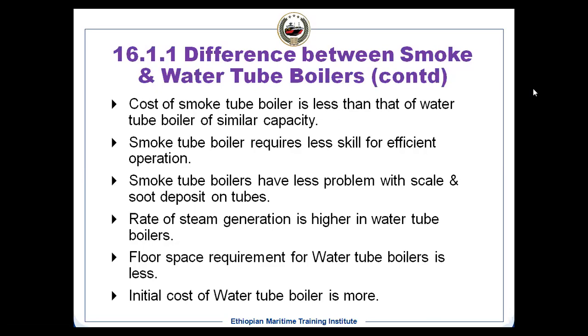Firstly, the water quality has to be maintained very well, and also the cleaning of the boiler, that is the furnace cleaning, etc., should be carried out much more stringently. Smoke tube boilers, this is the same point we were talking about earlier, have much less problem with scale and soot deposit on the tubes.